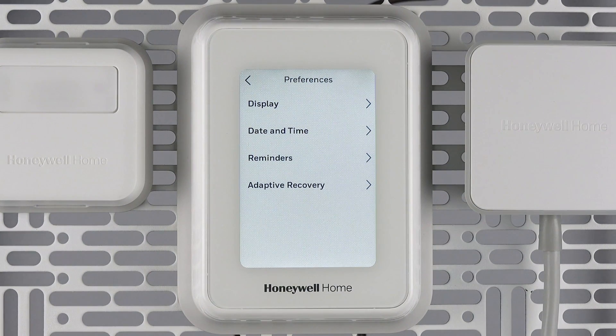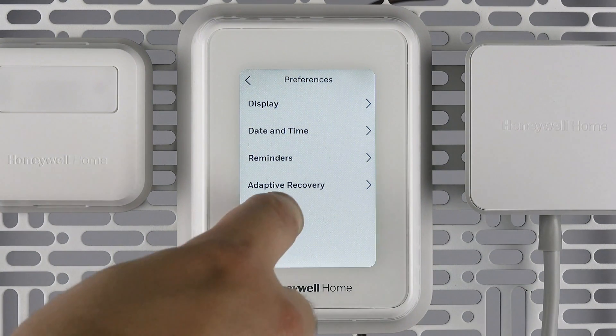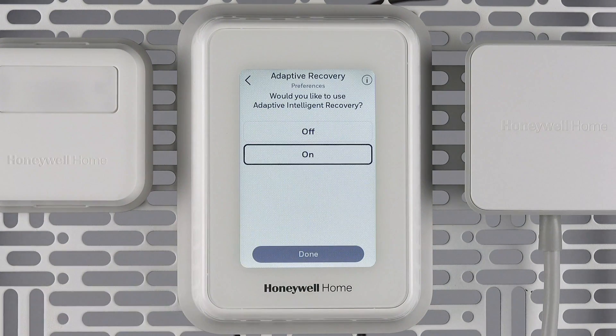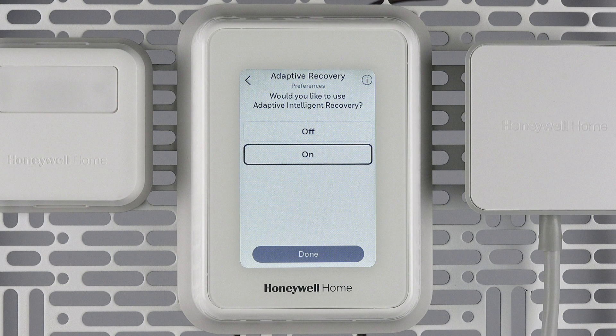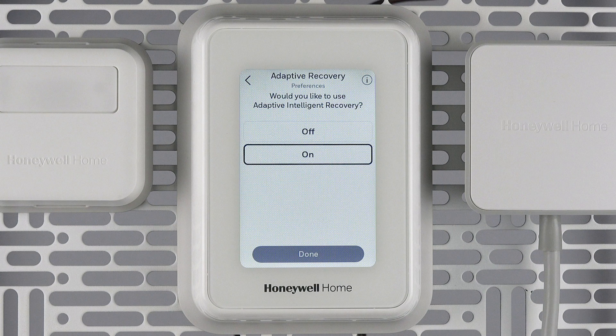Lastly, Adaptive Recovery. Adaptive Recovery allows your thermostat to learn how long your home takes to reach a certain set point. Using this data, it can turn on your heating or cooling earlier than your schedule periods to make sure you are at the desired temperature at the start of the schedule period.